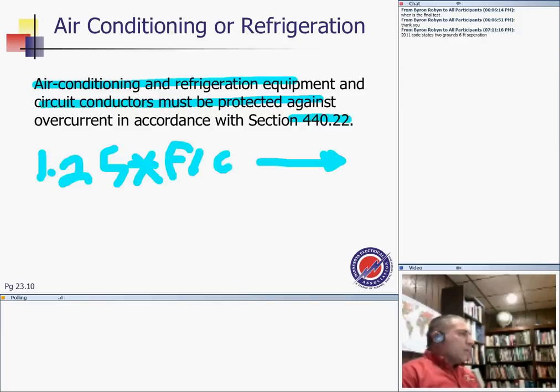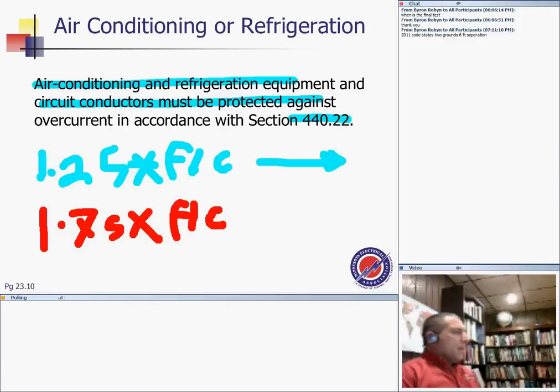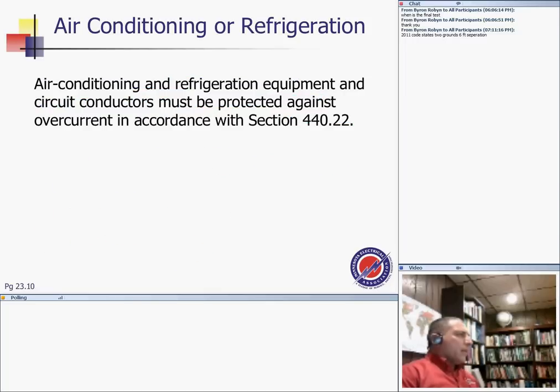The overload for AC system. I don't know how many of you guys have done that. They go 1.75 times load current of the AC system, full load current. And for this, guys, why the conductor can be smaller than the overcurrent device, because this equipment has an overload protection, like motors. I don't know if you guys have seen this scenario, which I hear all the time.